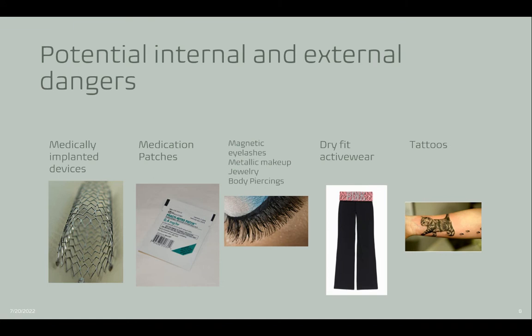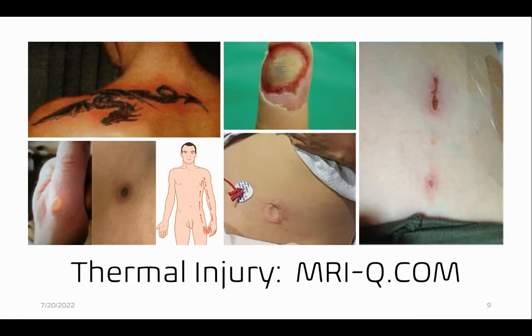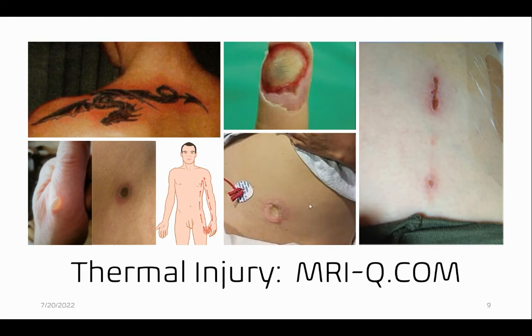Potential internal and external dangers for the MRI environment include medically implanted devices, medication patches, magnetic eyelashes, metallic makeup, jewelry, body piercings, dry fit active wear, and tattoos. The reason these objects are potential dangers is because metal or skin-to-skin contact can actually cause that skin to heat up in the MRI environment. Here we see some images from mriq.com of a tattoo-related thermal injury, skin-to-skin contact while the patient was in the MRI suite, a pulse ox thermal injury, an EKG lead thermal injury, and this is from the dry fit active wear like yoga pants that have thin metallic fibers within. So there is a burn danger for our patients as well.